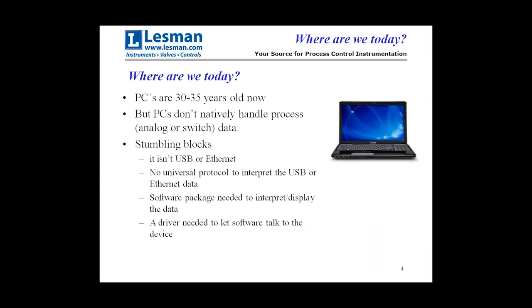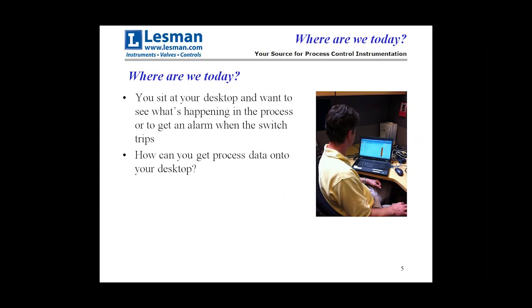PCs have been out there for 30 to 35 years now. The issue, of course, is PCs do not natively handle process data — there's no set of terminals on a PC where you can screw a thermocouple into it and get any data out. The stumbling blocks are: the PC wants to talk USB or Ethernet; there's no universal protocol to interpret that data; you need a software package to interpret or display it; and then there's the critical driver that talks to the device in the field, sitting between the software and the actual device.